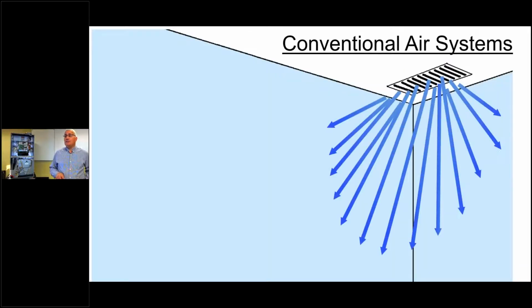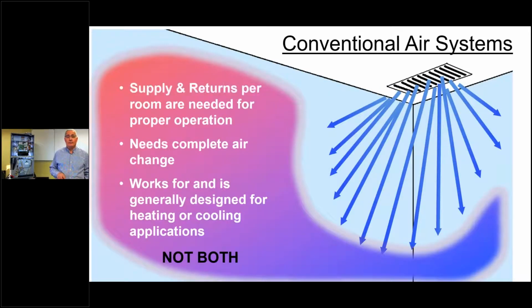What's nice about our system is how we move the air through these rooms. A conventional system, you're going to have a supply and return in a room. In the world of SpacePak, we just have our 2-inch outlet. We have one central return. I don't need a return per room. We are going to move the air via aspiration. So there's going to be a column of air blowing out of that outlet at high speed, which is going to create a vacuum around it, and the air around it will now get blended in.